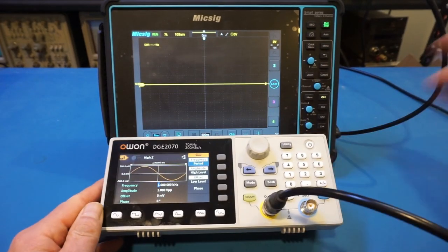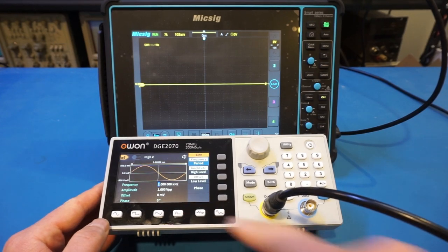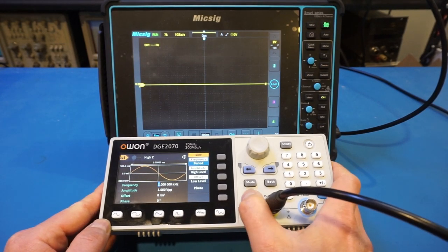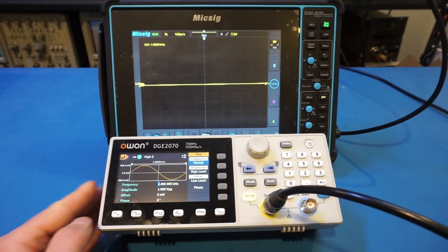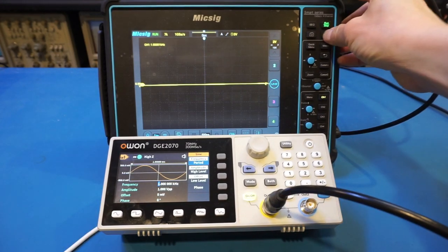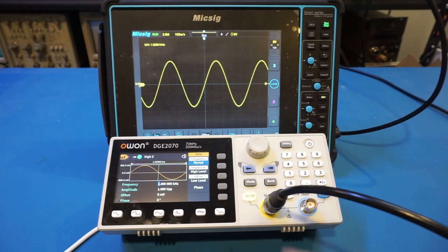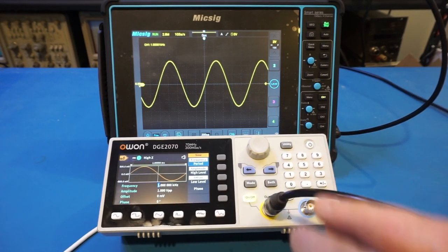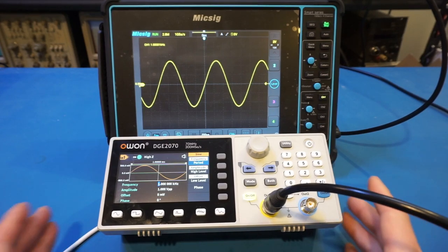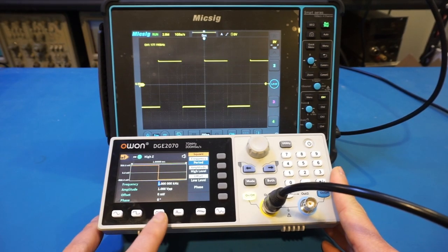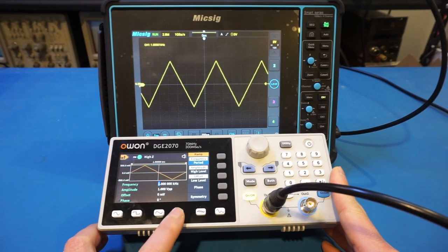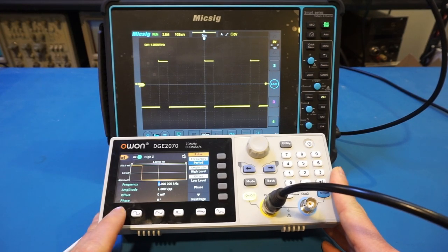The factory has defaulted to a sinusoidal waveform at one kilohertz. Let's enable the output and adjust the scope to acquire the signal. That's a one volt peak-to-peak one kilohertz sinusoidal. One neat feature of this DGE2070 is that commonly used waveforms are at the bottom — you can press those buttons and they will swap between different waveforms with just one button operation, whereas on the 962E you have to do two button presses to change between waveforms.